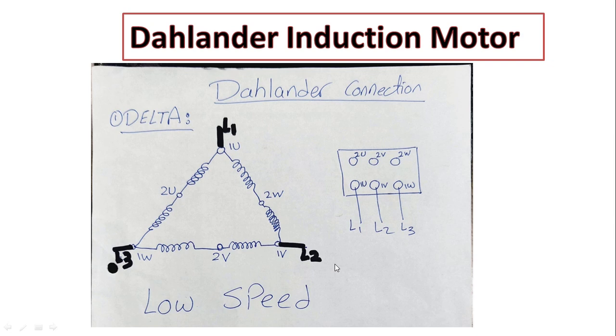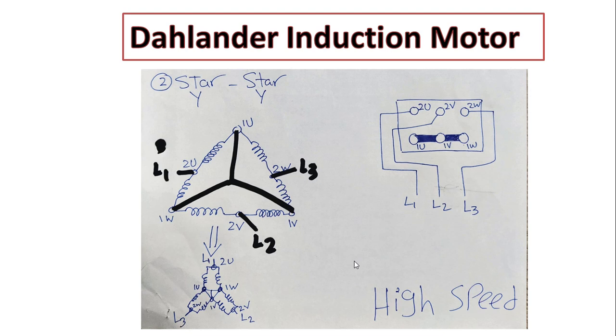But what if we want to connect it as star-star connection or double star connection? Here we will get the high speed feature, but we have to connect it in a different way. As you can see, the power supply will be connected to 2U, 2V, 2W.